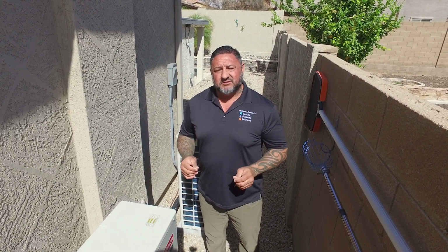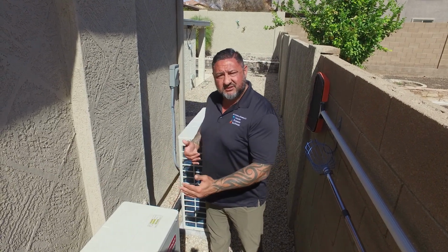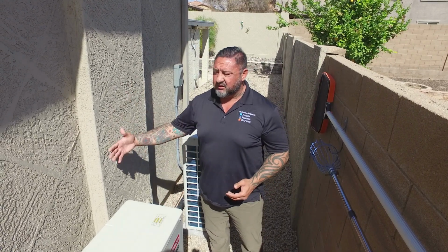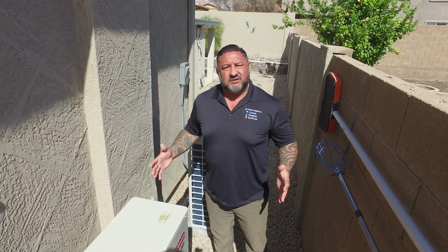It's not 95 degrees in the middle of summer. So I always recommend to our customers to let me get this off the wall as much as we can. Let me get them away from each other as much as they can so they're not stealing each other's air and they can breathe. And you can see, for example, in this situation, we've got a solid wall here and we've got a solid wall right here. So that's going to restrict airflow.